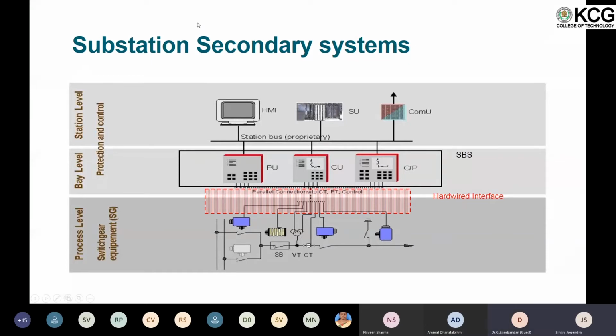This shows one particular part of the substation with the circuit breaker, VT, CT, and the control protection relays. In National Grid we call this a standard-based solution - standardized to reduce engineering inputs. All these are hardwired, meaning copper wiring goes from field equipment to the protection relays.